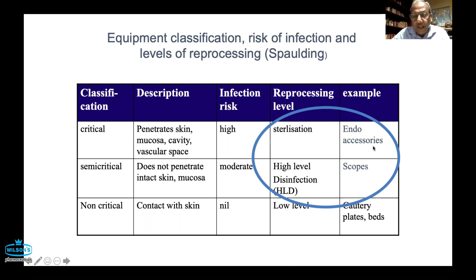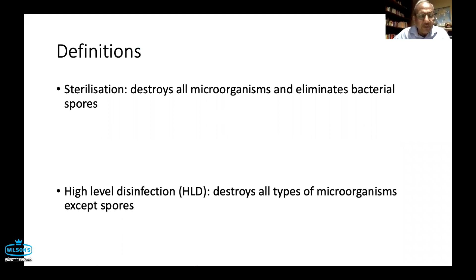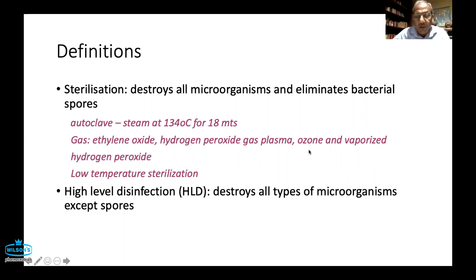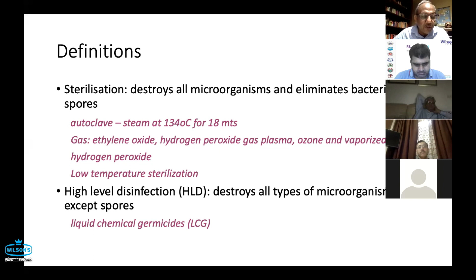So therefore, they undergo high-level disinfection, HLD, which is basically a terminology for disinfection. Now, sterilization destroys all microorganisms and eliminates bacterial spores. We all know that autoclaving is the best method, but then there are ethylene oxide sterilization, and then there are other newer methods of hydrogen peroxide gas plasma, ozone, and vaporized hydrogen peroxide. And now people even talk about low temperature sterilization because of the equipment which can be damaged by sterilization. High level disinfection destroys all types of microorganisms. And here you use liquid chemical germicides, like Cidex that we've been using routinely.